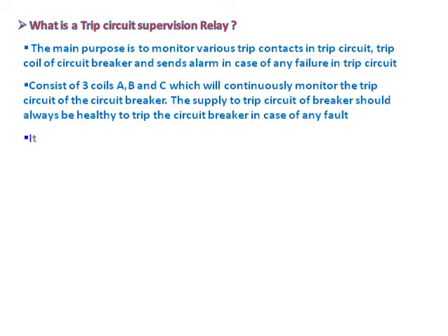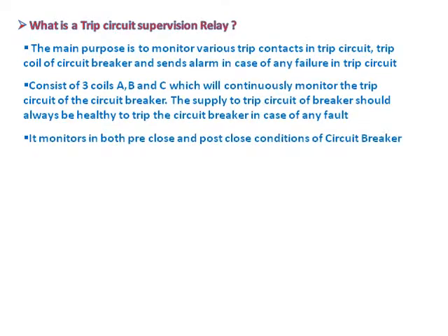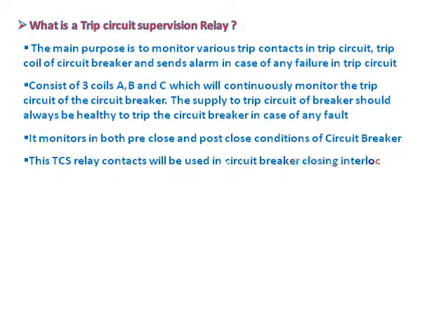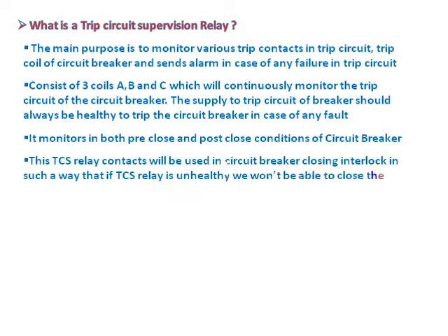It monitors in both pre-close and post-close conditions of the circuit breaker. The TCS relay contacts will be used in the circuit breaker closing interlock in such a way that if the TCS relay is unhealthy, we won't be able to close the circuit breaker.